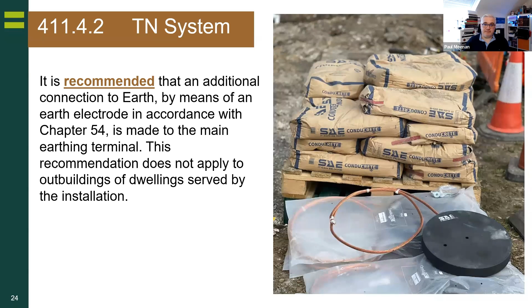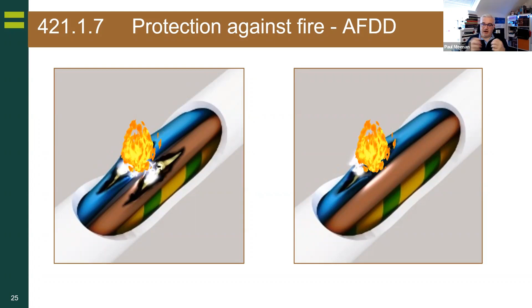421.1.7, protection against fire, AFDD. Now, for those who may not know about AFDDs, I flew to Austria when they came out to do some testing with the guys at Eaton to understand them better. Effectively, they're a microprocessor that sits in a device and looks for noise on the waveform. But fundamentally, what they do is look for series breaks in a conductor, whether it be line or neutral, or parallel breaks, which may not get picked up by an RCD. What can happen is that break in the conductor can allow temperatures to increase. That then allows the PVC to oxidize. As that copper melts, it causes gas. Eventually, you get carbon. It allows voltage to track. Boom, ignition. You then get a fire.